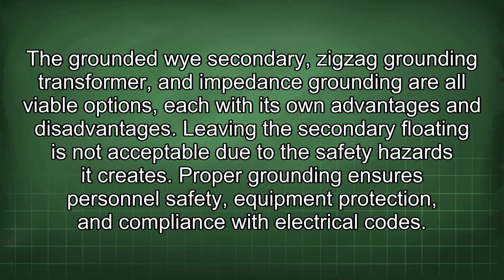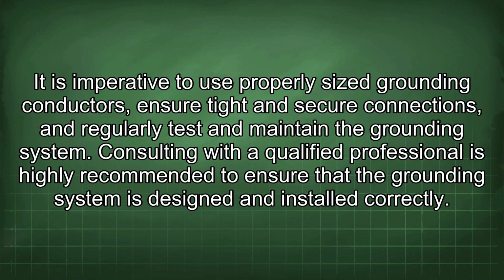Proper grounding ensures personnel safety, equipment protection, and compliance with electrical codes. It is imperative to use properly sized grounding conductors, ensure tight and secure connections, and regularly test and maintain the grounding system. Consulting with a qualified professional is highly recommended to ensure that the grounding system is designed and installed correctly.